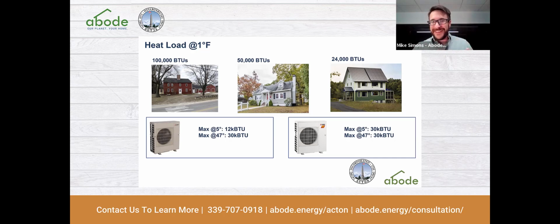What's neat with mini splits is that all you need to do is put in 2 outdoor units. Now you have enough horsepower and hardware to power this 50,000 BTU house. So that's one approach. It's like, all right, well, we'll just put in more hardware. And that may not be a bad approach for this house, because this 30,000 BTU unit, the most amount of indoor units that it can handle is 3.